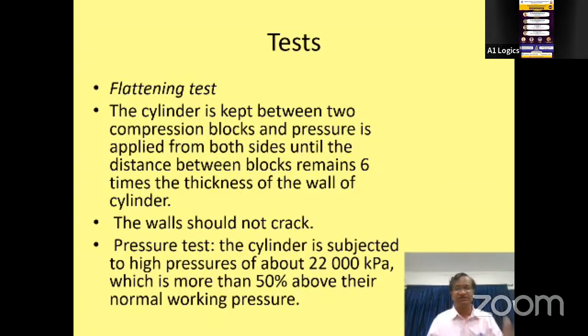The cylinder is subjected to a pressure of 22,000 kPa, which is more than 50% above their normal working pressure. Beyond that increase, nothing happens. So we should not transfill the cylinder.